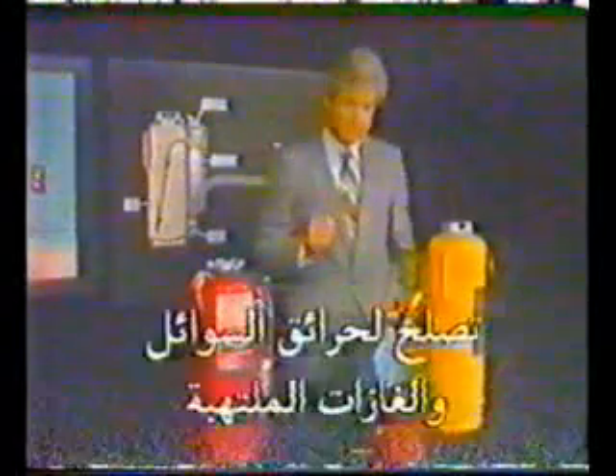The fifth type of extinguishing agent we'll look at is halogenated agents or halogens. These are special liquids or gases that work chemically to extinguish a fire. Halogens, like dry chemicals, break up the chemical chain reaction of combustion. Halogens are effective for fighting flammable liquid and gas fires as well as most fires involving solid combustible materials. They're especially good for fighting electrical fires because they don't conduct electricity and they leave no residue on sensitive parts.